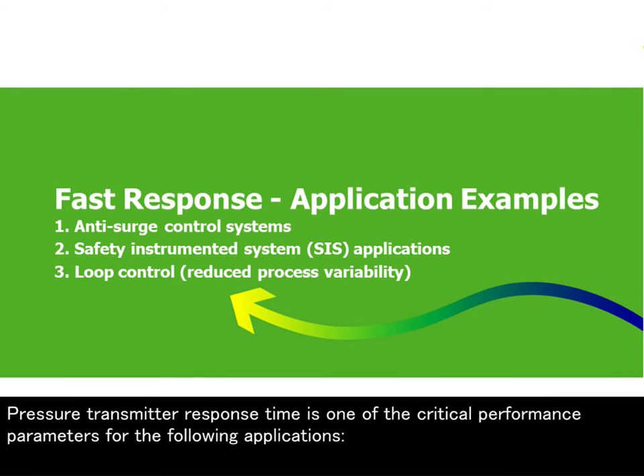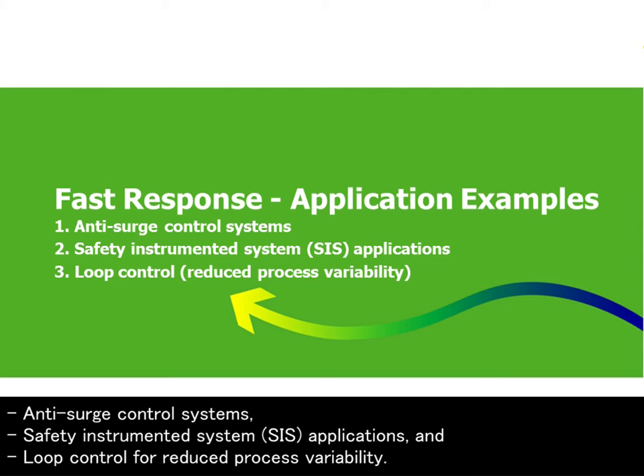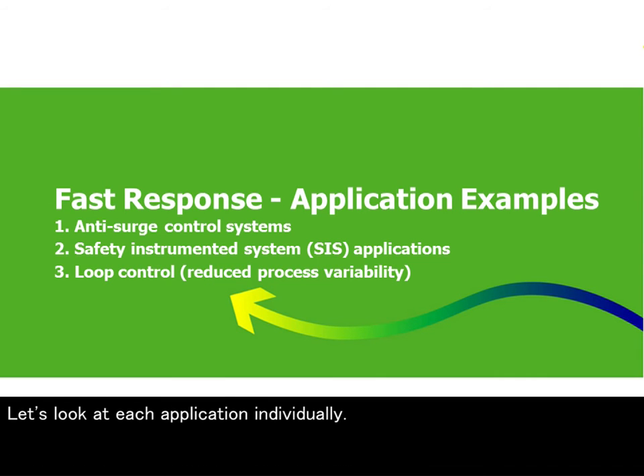This faster response time now allows both the EJX and EJAE to be used in high-speed applications. Pressure transmitter response time is one of the critical performance parameters for the following applications: anti-surge control systems, safety instrumented system (SIS) applications, and loop control for reduced process variability. Let's look at each application individually.